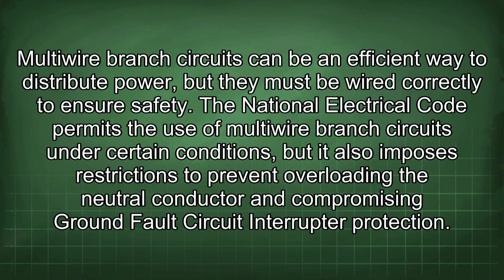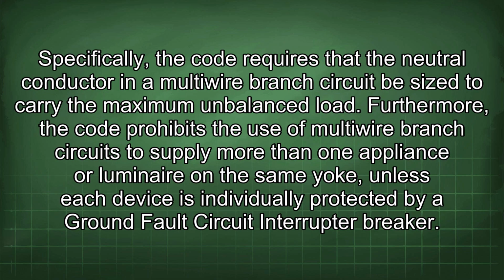Multi-wire branch circuits can be an efficient way to distribute power, but they must be wired correctly to ensure safety. The National Electrical Code permits the use of multi-wire branch circuits under certain conditions, but it also imposes restrictions to prevent overloading the neutral conductor and compromising ground fault circuit interrupter protection. Specifically, the code requires that the neutral conductor in a multi-wire branch circuit be sized to carry the maximum unbalanced load. Furthermore, the code prohibits the use of multi-wire branch circuits to supply more than one appliance or luminaire on the same yoke, unless each device is individually protected by a ground fault circuit interrupter breaker.